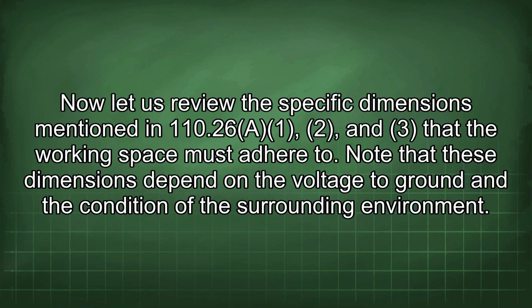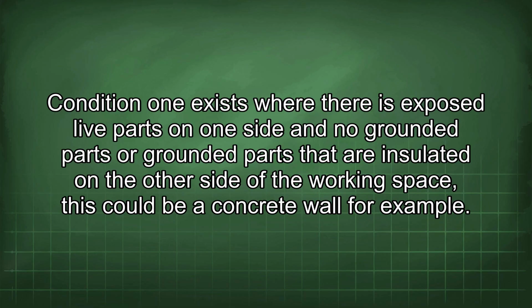Now let us review the specific dimensions mentioned in 110.26(A)(1), (2), and (3) that the working space must adhere to. Note that these dimensions depend on the voltage to ground and the condition of the surrounding environment. Condition 1 exists where there are exposed live parts on one side and no grounded parts, or grounded parts that are insulated, on the other side of the working space.